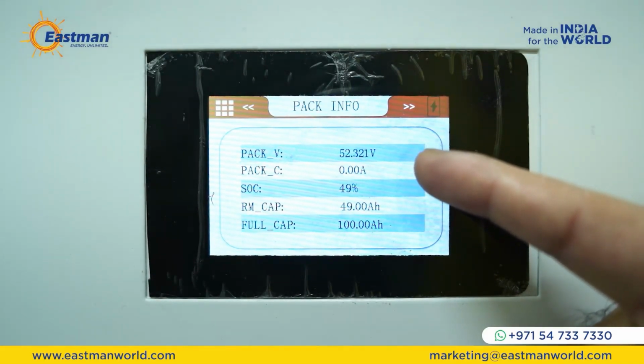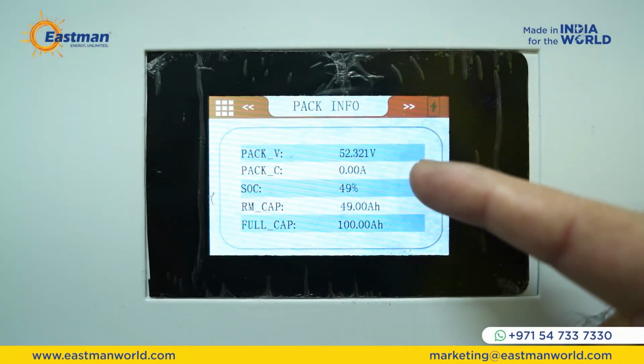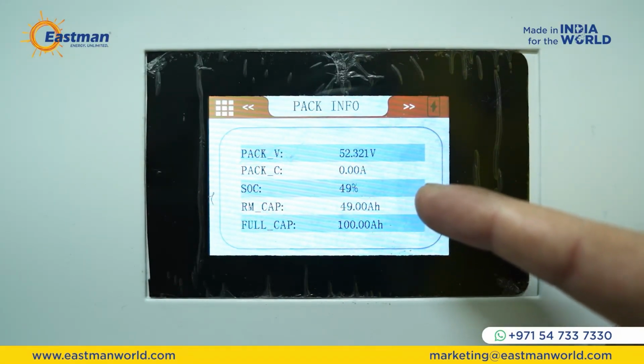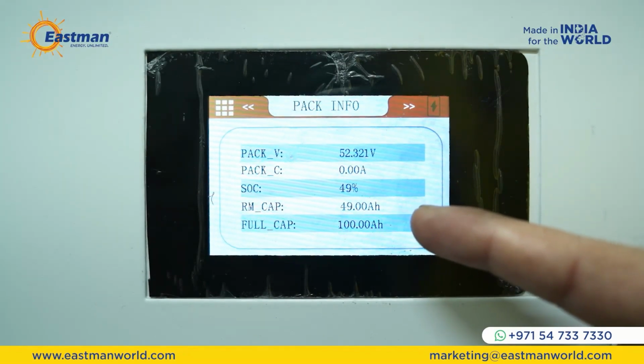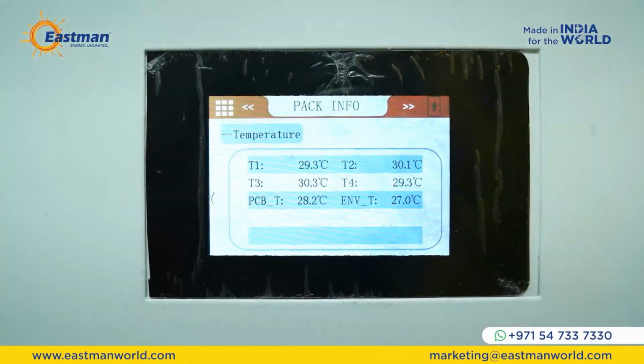Pack voltage now. Pack current 0, no inverter connected. Battery charge 49%. Remaining capacity 49 ampere hours, full capacity 100 ampere hours.